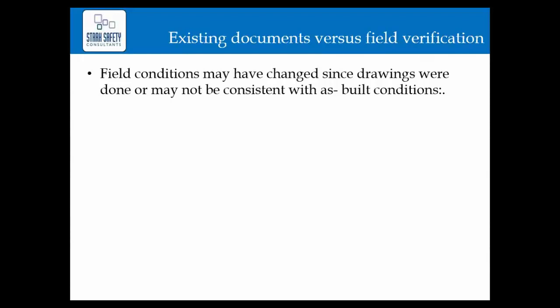Field conditions — why it's important to get them is you may have a good document, but those field conditions may have changed since that drawing was done, and it may not be consistent with any as-built. So from brand new construction, you get an engineered construction diagram, then you actually build that and put the equipment in, and someone should be documenting as-built. We have a lot of steps, and we do have some variation that could come into play without verifying the field conditions.